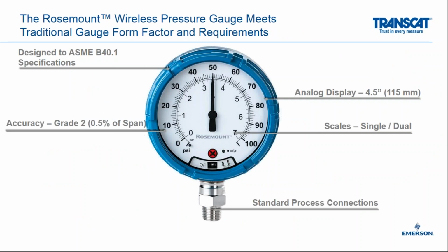From a technical standpoint, it's designed to ASME B40.1 specifications, very standard gauge specifications, an accuracy of grade 2, that's 0.5% of span. It has an analog display, and this is traditionally considered a digital gauge, but it's interesting to see that it still has an analog display because you want to be able to see this not just right up in front of a gauge, but oftentimes you need to see a gauge when you're 10 feet or 20 feet away, and so that needle can still be an important part of a gauge. Certainly single or dual scales, again, very common for any sort of gauge, and then a very standard process connection.